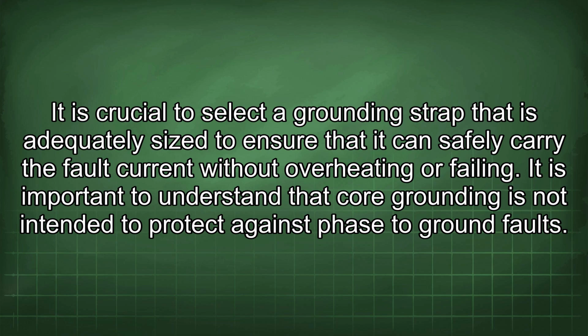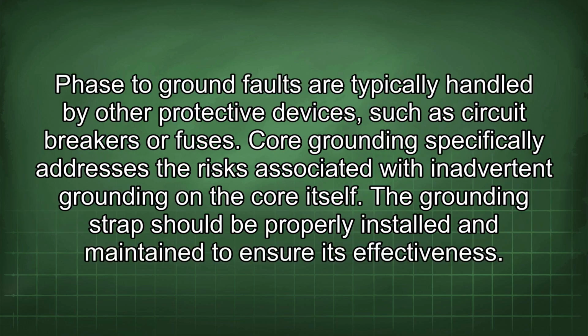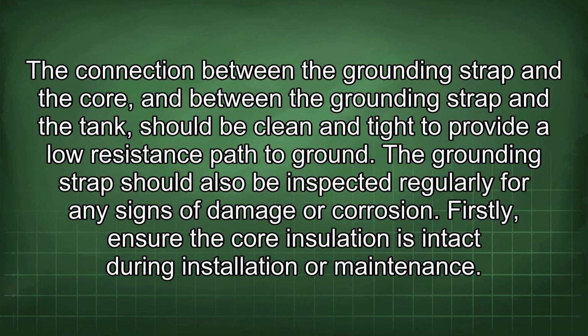It is important to understand that core grounding is not intended to protect against phase-to-ground faults. Phase-to-ground faults are typically handled by other protective devices, such as circuit breakers or fuses. Core grounding specifically addresses the risks associated with inadvertent grounding on the core itself. The grounding strap should be properly installed and maintained to ensure its effectiveness. The connection between the grounding strap and the core, and between the grounding strap and the tank, should be clean and tight to provide a low resistance path to ground. The grounding strap should also be inspected regularly for any signs of damage or corrosion.